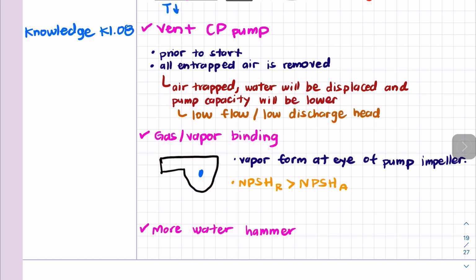Now we are also going to see the importance of venting a centrifugal pump, or what I call a CP pump. Venting a CP is important because it removes air from the pump and the suction piping and prevents air pockets from forming inside the pump. Air pockets can disrupt the flow of liquid through the pump and reduce the pump's efficiency. We are trying to be as efficient as we can in a power plant, so that's why it's important. This can also cause cavitation and damage to the pump over time. We're going to get to cavitation in a little bit, but there are a few ways to vent a centrifugal pump.